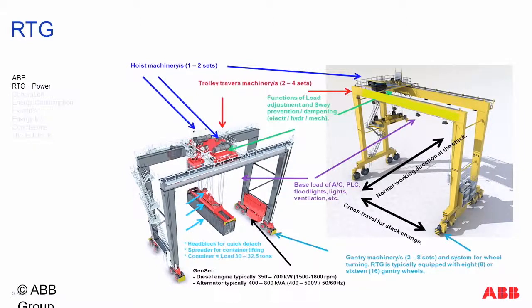The configuration may vary. Hoist machinery could have 1 or 2 sets, trolley travel 2 to 4 sets, gantry machinery 2 to 8 sets, and the diesel engine size may vary from 350 to 700. The speed also varies - the electrical generator inside could be 50 or 60 hertz, depending on 1,500 or 1,800 RPM, whichever is available. There are also other considerations related to the type of generator inside, but now we'll go into it a little more.